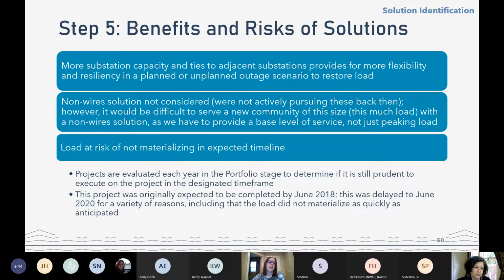Benefits and risks of solutions: more substation capacity and ties to adjacent substations gives us more flexibility and resiliency in a planned or unplanned outage scenario. We did not consider non-wire solutions back in the day. However, it would be difficult to serve a new community of this size with this much load with a non-wire solution, because we have to provide that base level of service. We have to put wires in the ground to serve this load - we can't just serve new homes with a non-wire solution. We have to build physical infrastructure to serve it. And a risk is that the load was not going to materialize in the expected timeline.